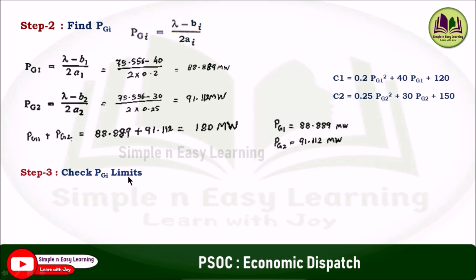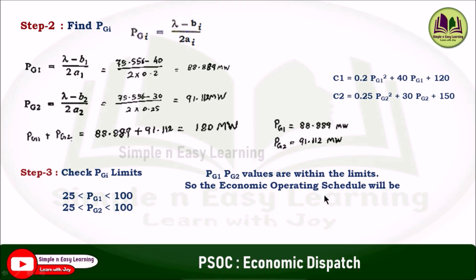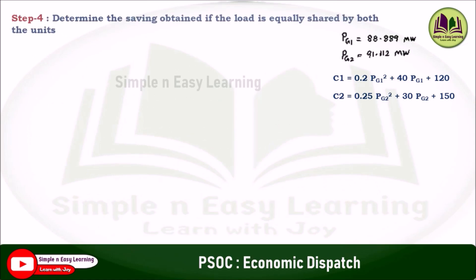Step 3: check the PGi limits. The limits are given from 25 to 100. PG1 lies within the limit and PG2 also lies within the limit. So the economic operating schedule will be PG1 equal to 88.889 megawatt and PG2 equal to 91.112 megawatt.